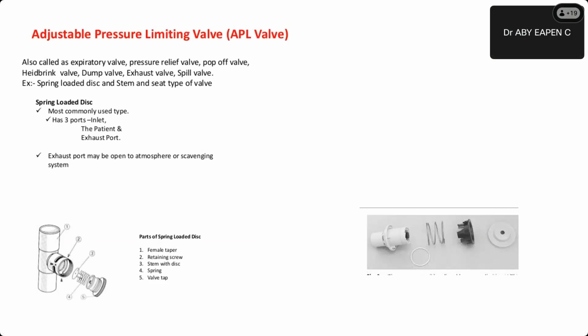So this is also called the adjustable pressure limiting valve, which has a spring-loaded disc, commonly used in the inlet or patient or exhaust port. These are all the locations where it may be situated, and it can be used both in spontaneous and controlled ventilation. So in controlled ventilation, you are supposed to keep it as much as possible closed, whereas in spontaneous ventilation, it should be kept fully open.